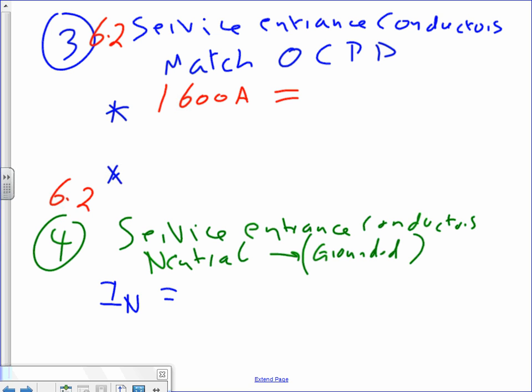So think about this one. Divide this one by what to get you close to 400? 4, very easy. And what does 4 mean? 4, gentlemen, means 4 of this: 3 phases and neutral, 3 phases and neutral, 4 cables, okay? Good, so that'll give me 400.